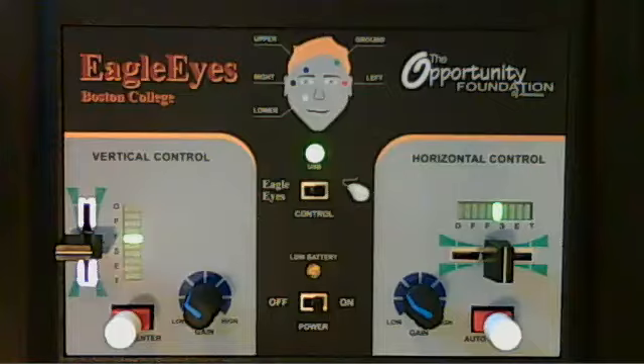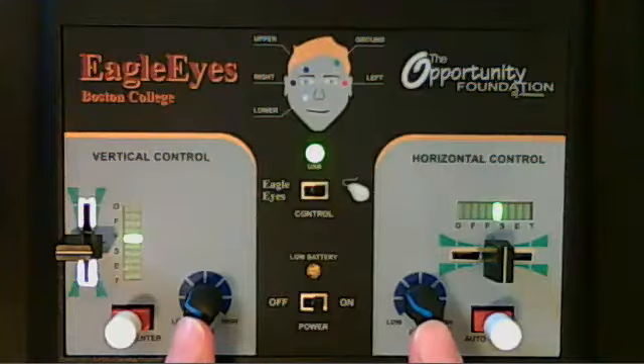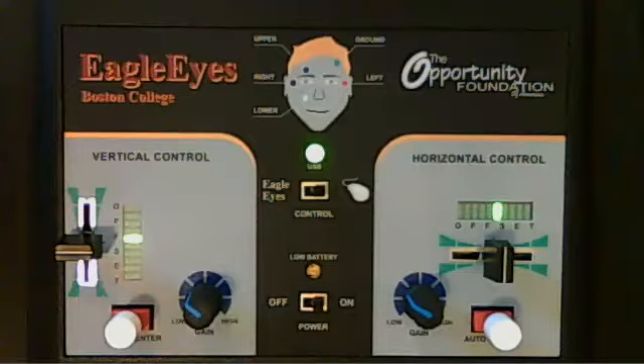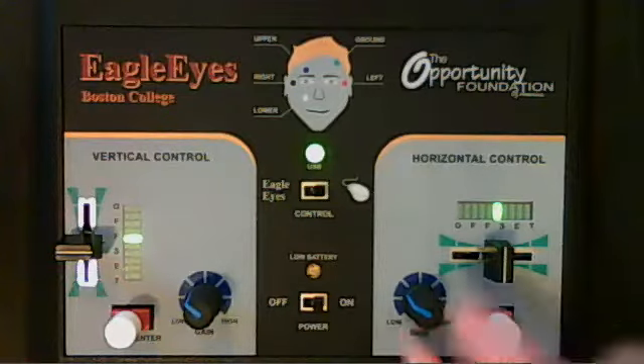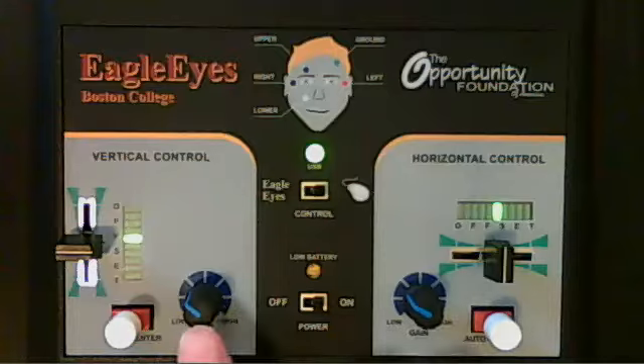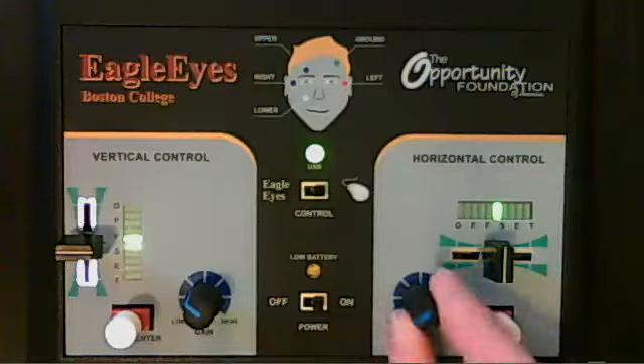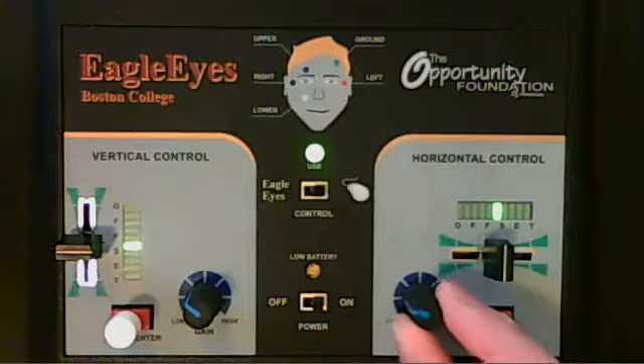Generally, once you've set the calibration, it won't need to be adjusted very often. Here we have the horizontal and vertical gain settings. The gain adjustment is really the sensitivity. It amplifies the signal. So if the user seems not to be able to access the entire area of the screen, we can increase those. Generally, we're going to have them in the 10 o'clock position, as you see on the screen. They go all the way down, and we're usually going to use about a 10 o'clock position for most users.